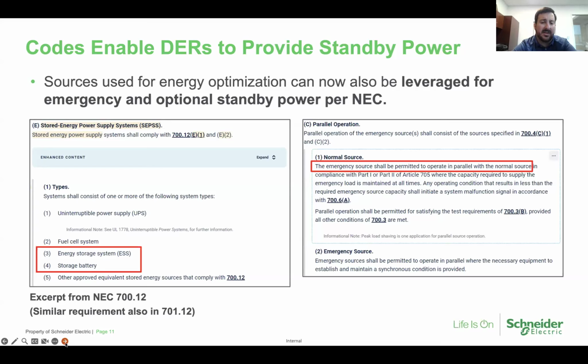But in this particular case, historically, energy storage systems, battery energy storage, beyond being used for UPS short-term applications, were either not mentioned in the code or in some applications specifically forbidden to be used as an extended outage source of power. But in the most recent editions of the National Electric Code, that's now being allowed.